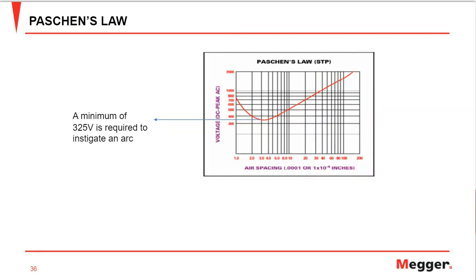Before heading to surge testing and its details, we'll understand what Paschen's law is. It's a good reference point for understanding why this test, conducted at the rated voltage, is not destructive, and to understand more about surge testing as well. This law explains why a high voltage test can determine the condition of a motor. As you see on the graph, it requires a minimum of 325 volts to instigate an arc, and that is when the two conductors are at a distance of 3/10,000 of an inch, which is a very small gap. So even if there are bare copper wires or bare copper turns, it would still need a minimum of 325 volts to instigate an arc.